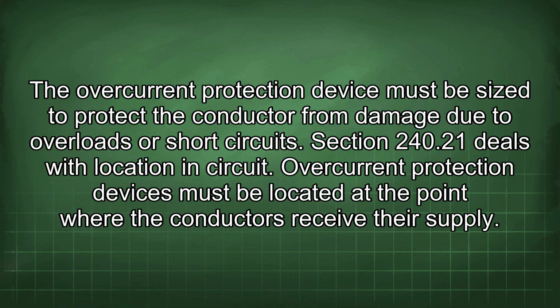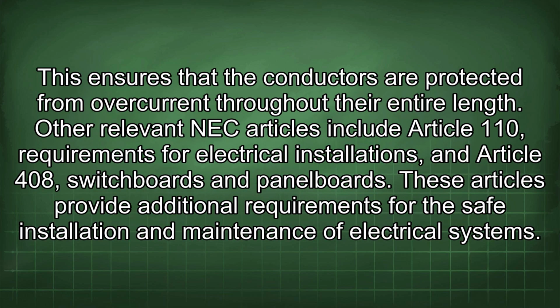Section 240.21 deals with location in circuit. Overcurrent protection devices must be located at the point where the conductors receive their supply. This ensures that the conductors are protected from overcurrent throughout their entire length. Other relevant NEC articles include Article 110, Requirements for Electrical Installations, and Article 408, Switchboards and Panel Boards. These articles provide additional requirements for the safe installation and maintenance of electrical systems.